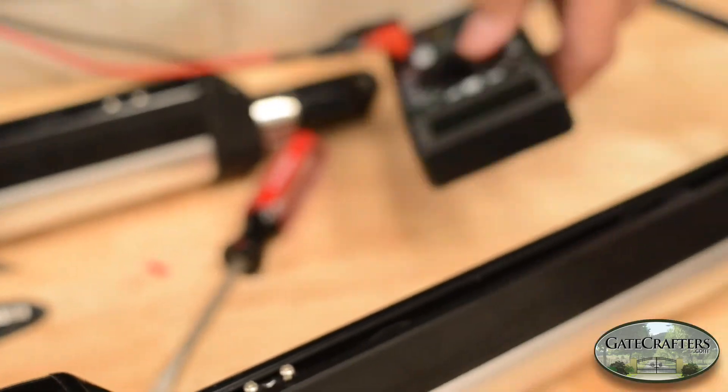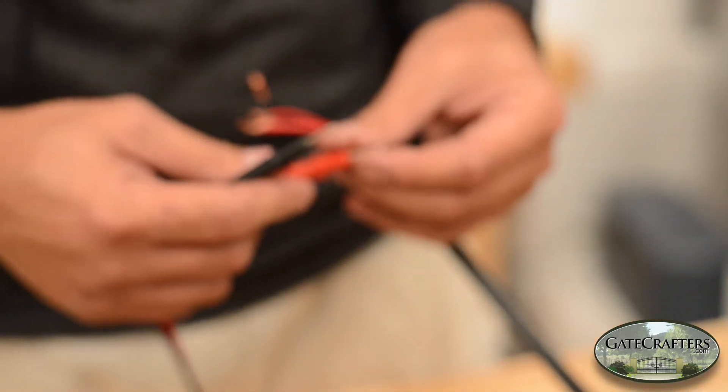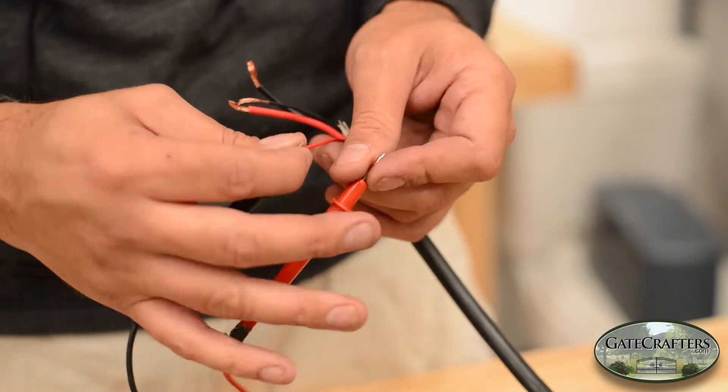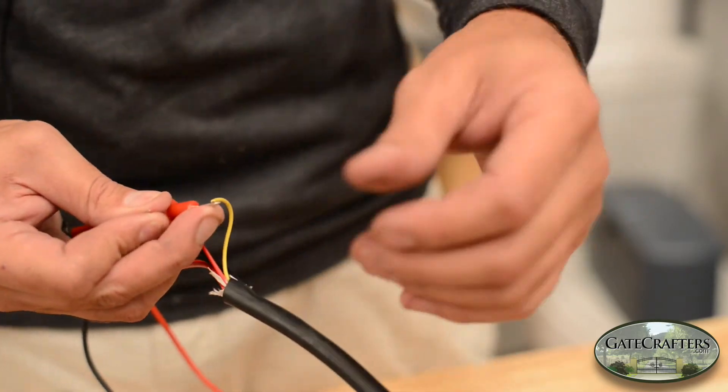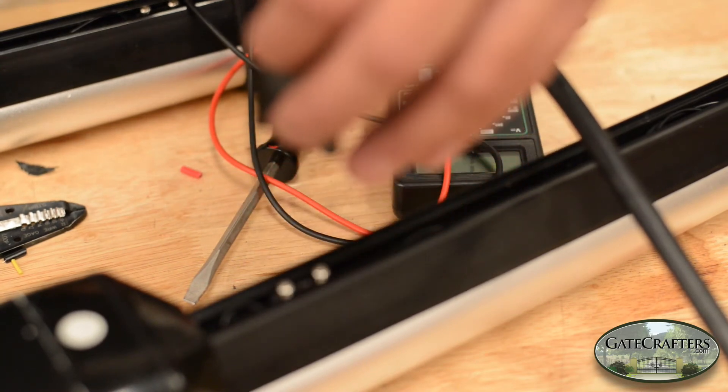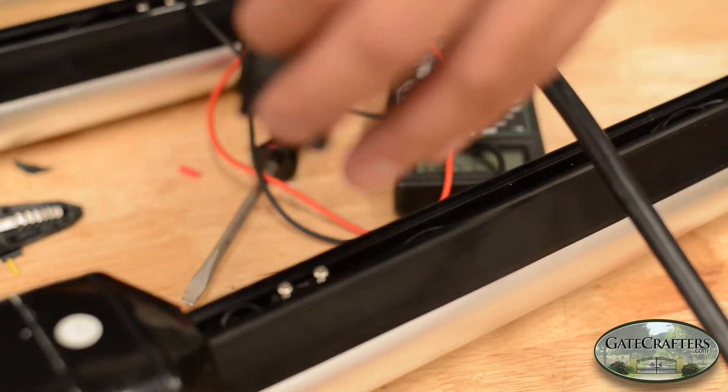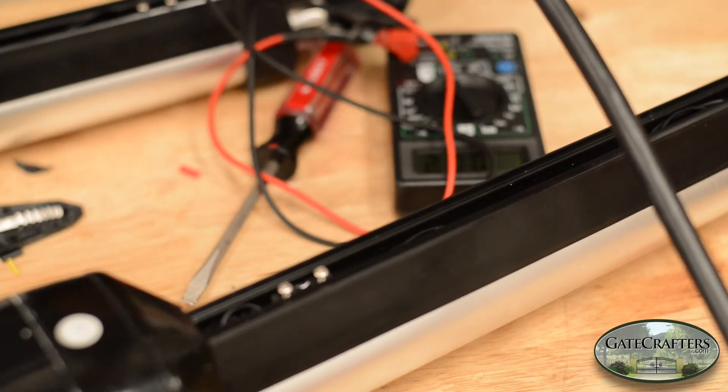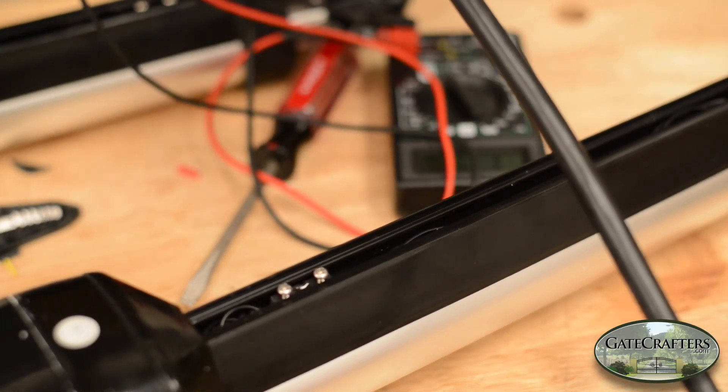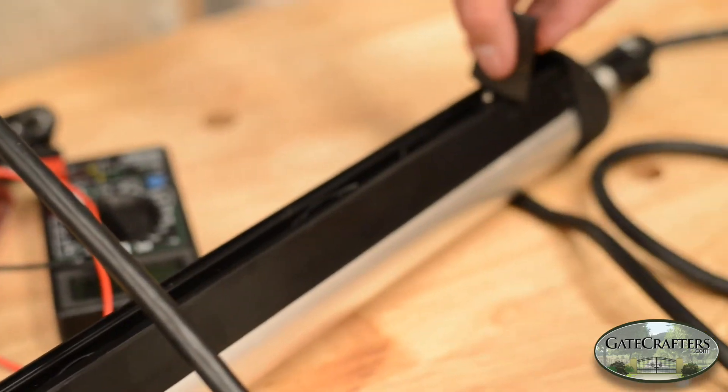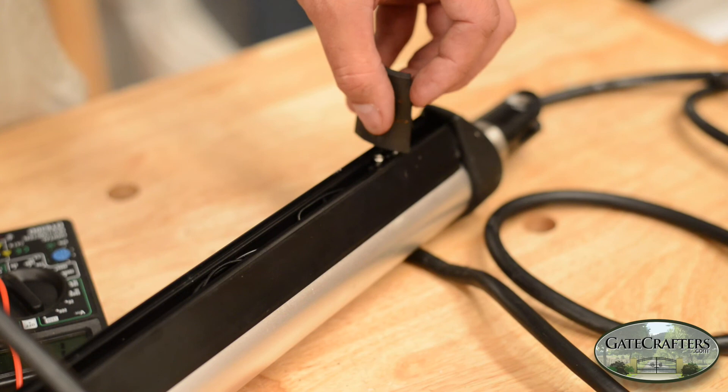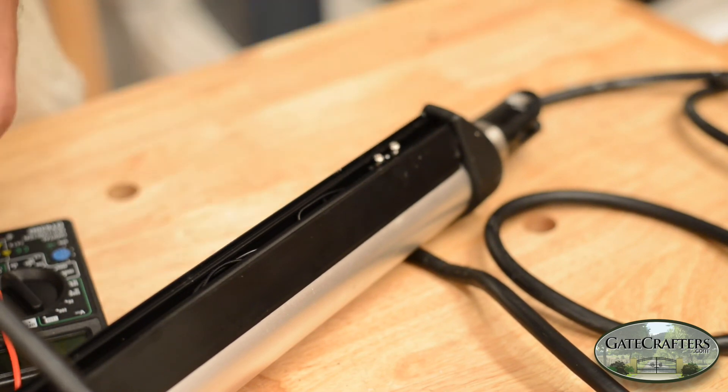So you can set the multimeter to continuity. The retracted limit is between red and yellow. You get that beeping noise. Take your magnet, put that over the magnet, and you'll see that it breaks the continuity, breaks the circuit. So that one's still good. We're doing this to make sure none of the wires fell off in the process, and it looks like we're good. Both the limit switches are still working, so this one's good to go.